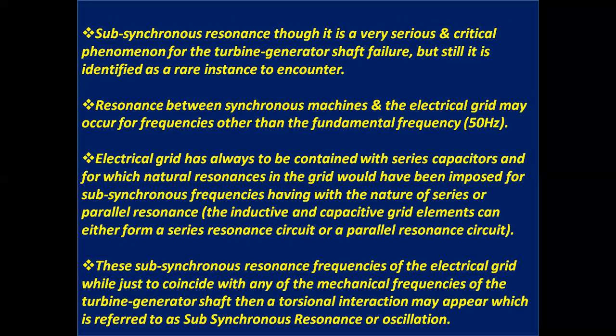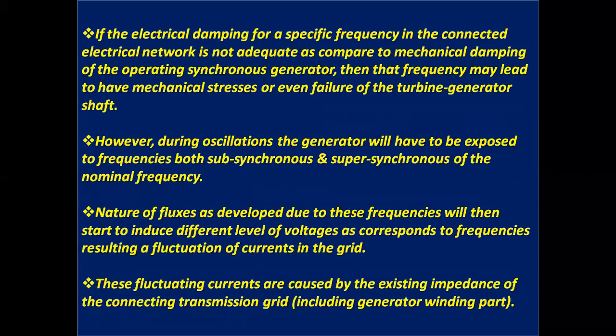That is, the inductive and capacitive grid elements can either form a series resonance circuit or a parallel resonance circuit. If these subsynchronous resonance frequencies of the electrical grid happen to coincide with any of the mechanical frequencies of the turbine generator shaft, then a torsional interaction may appear, which is referred to as subsynchronous resonance or oscillation. If the electrical damping for a specific frequency in the connected electrical network is not adequate as compared to the mechanical damping of the operating synchronous generator, then that frequency may lead to mechanical stresses or even failure of the turbine generator shaft.